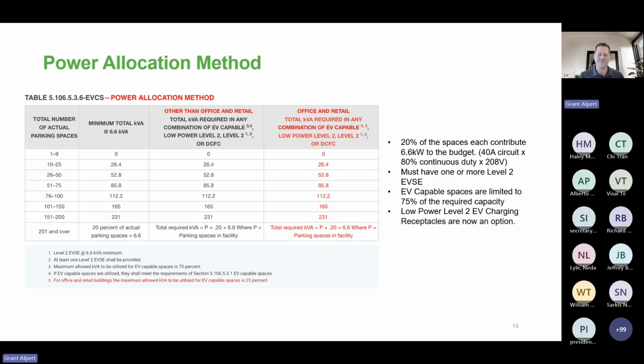So you could have a bunch of 3.2 kVA chargers, or just one 26 kVA charger. The only caveat is that you have to have 1 level 2 EVSE. So even if you just have one 26 kVA charger, there also has to be a level 2 EVSE. And then the other caveat is that EV capable spaces can only be 75% of the required capacity. So in this first column, 26 kVA, 75% of that can be EV capable, just the conduit and the panel, which is 20-ish kVA, and then the other 6 or so would be required to be an EVSE.